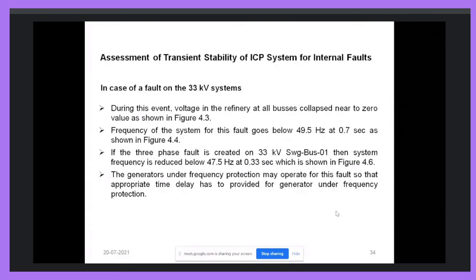Yes, sir. Okay. So I have considered the different types of fault in the system and performed the transient stability analysis, like the fault at different locations of the system. As we have seen in the single line diagram, the different voltage levels are there: 33 kV, 6.6 kV, 415 volt. These are the different distribution voltage levels in the system. So I have considered the fault in every voltage level of the system and determined the parameters.